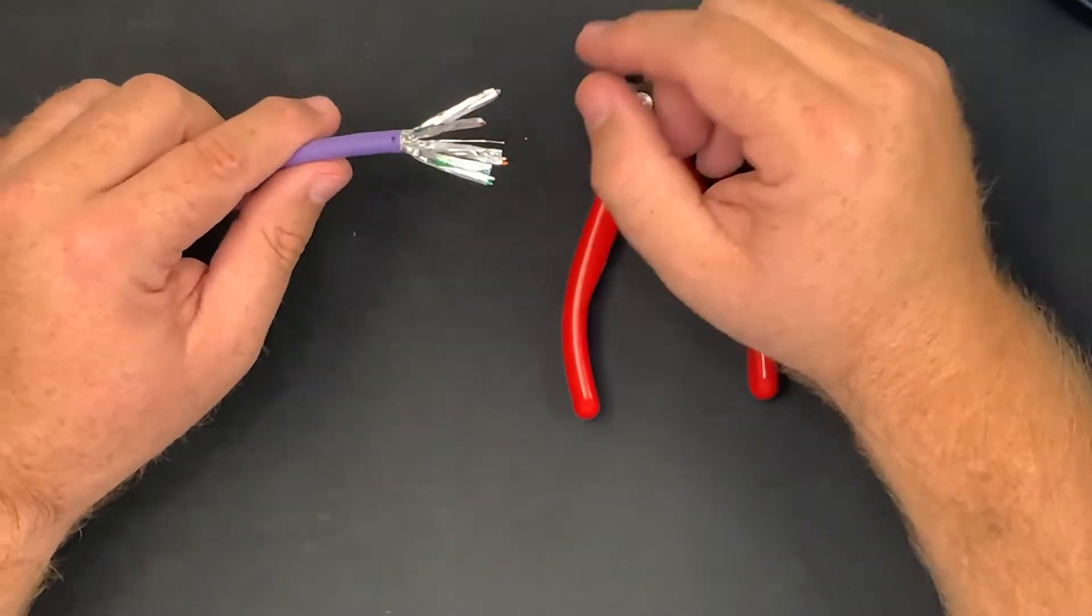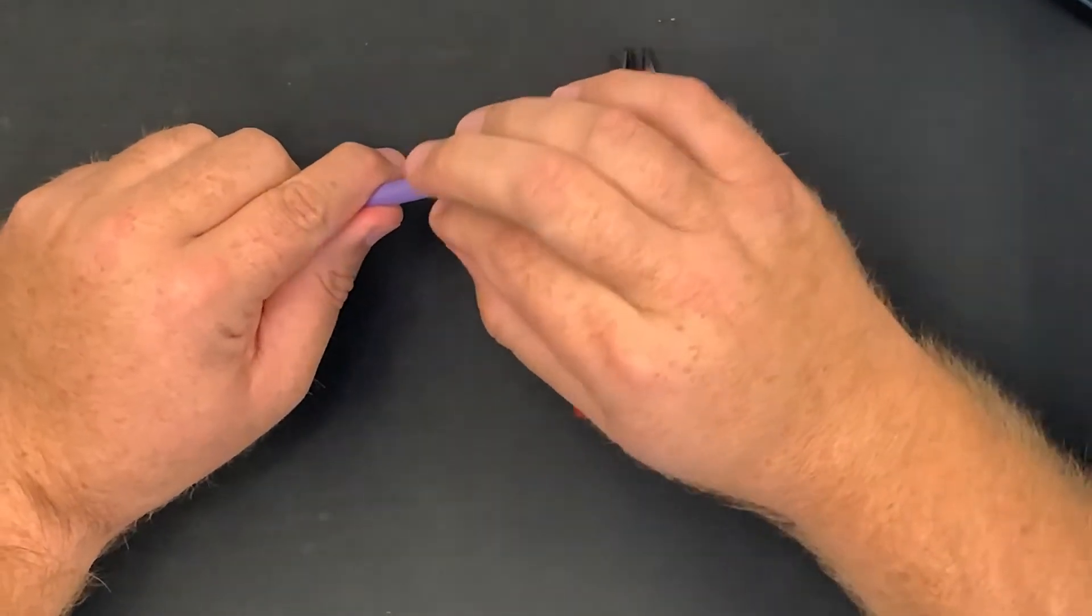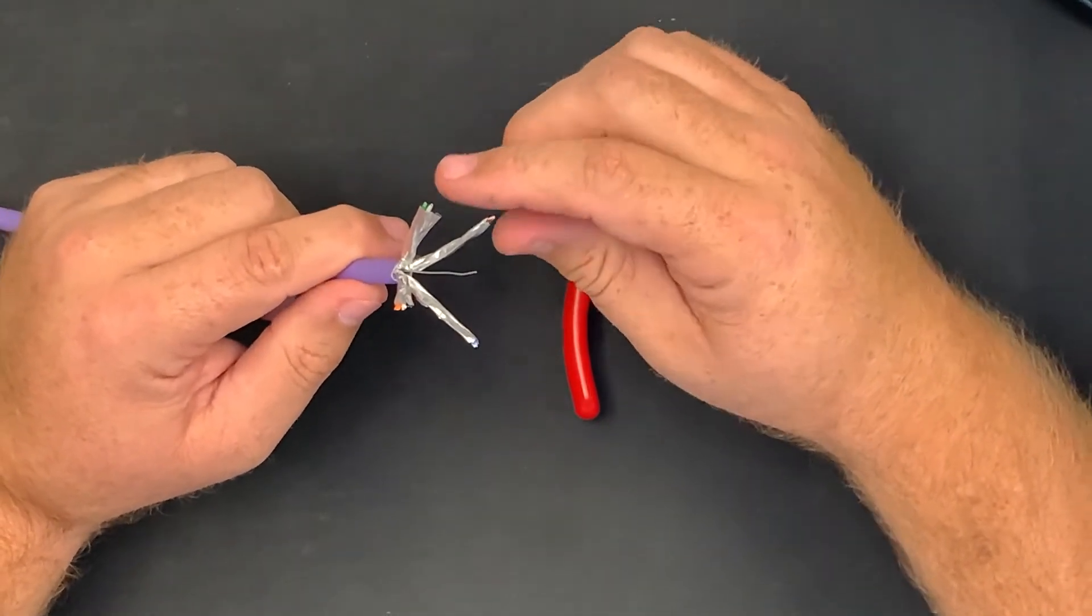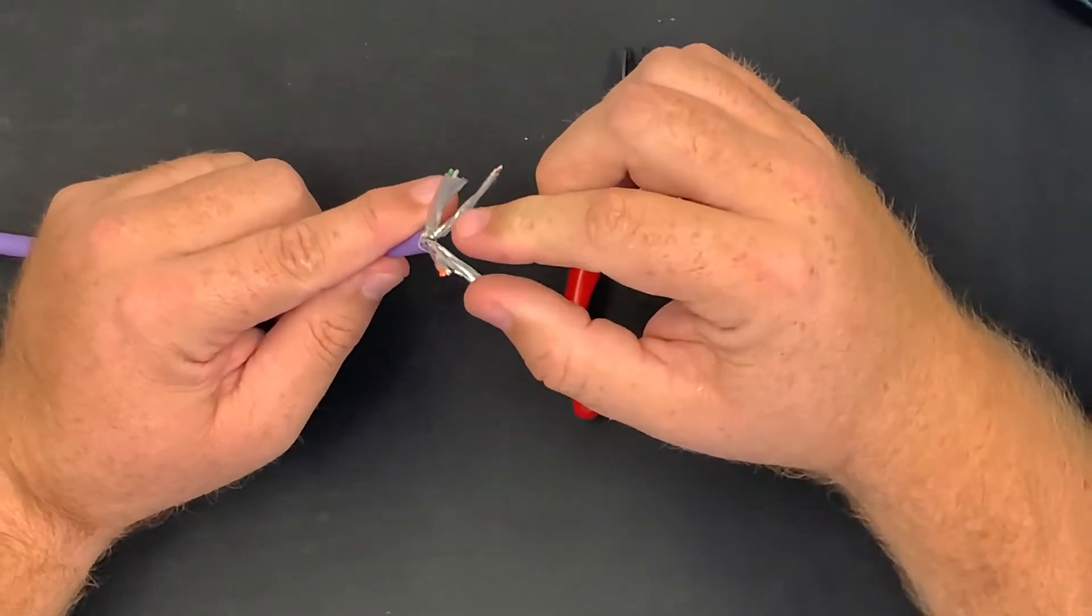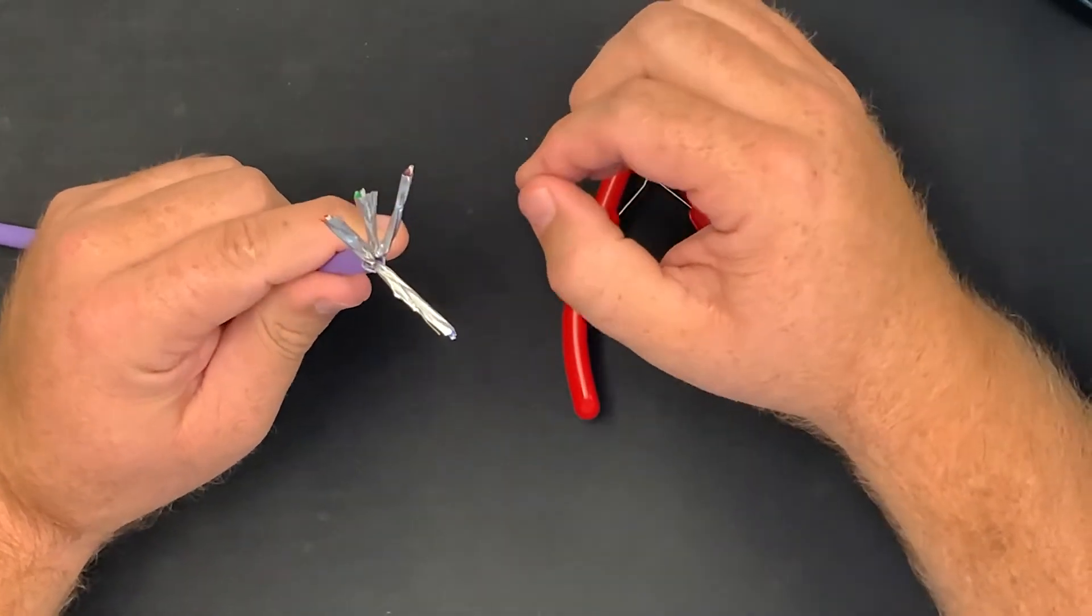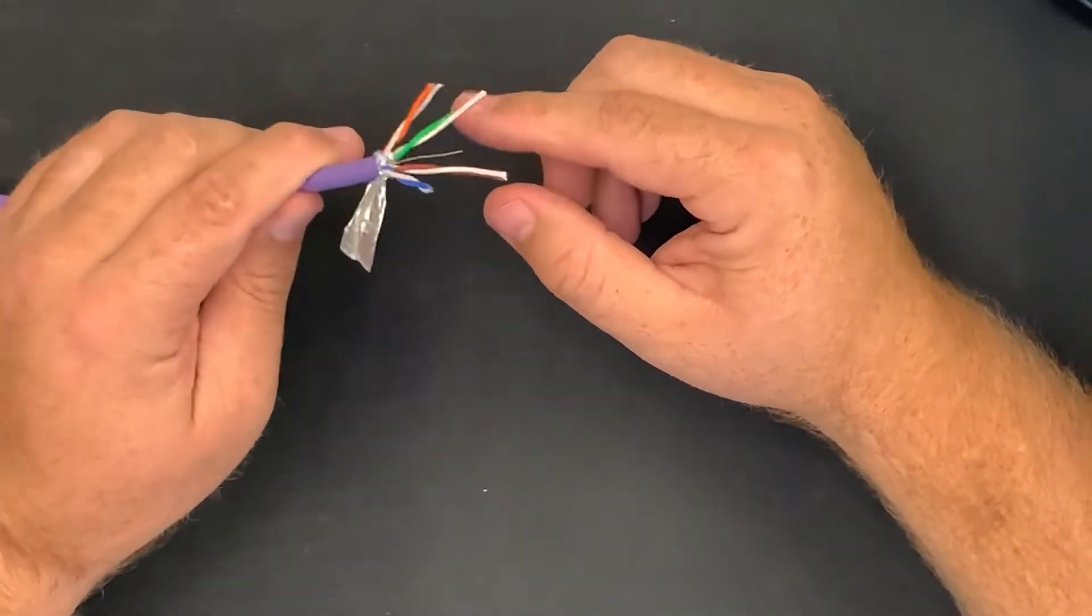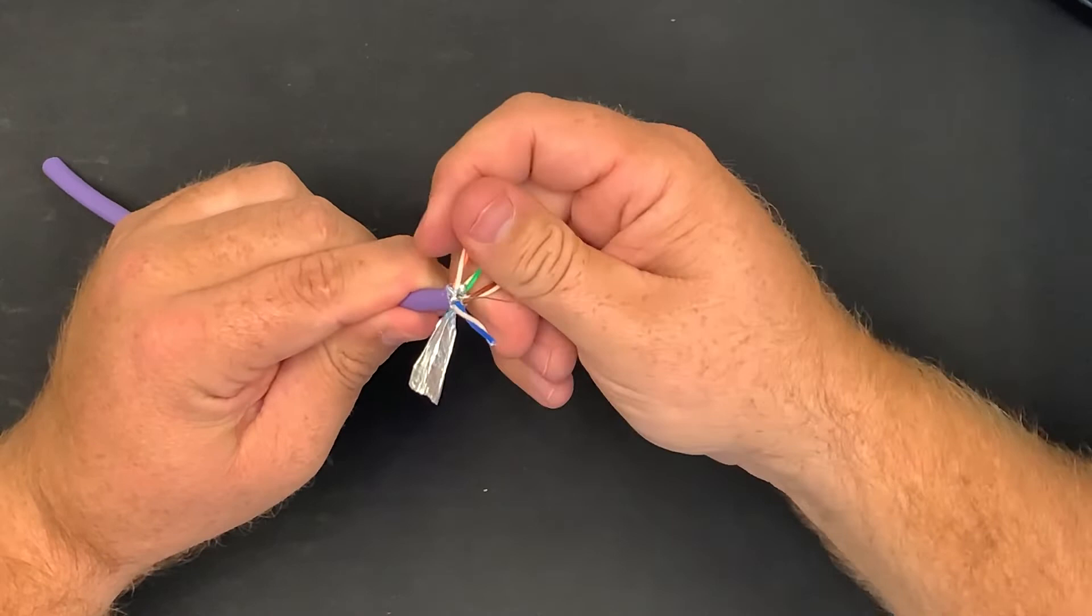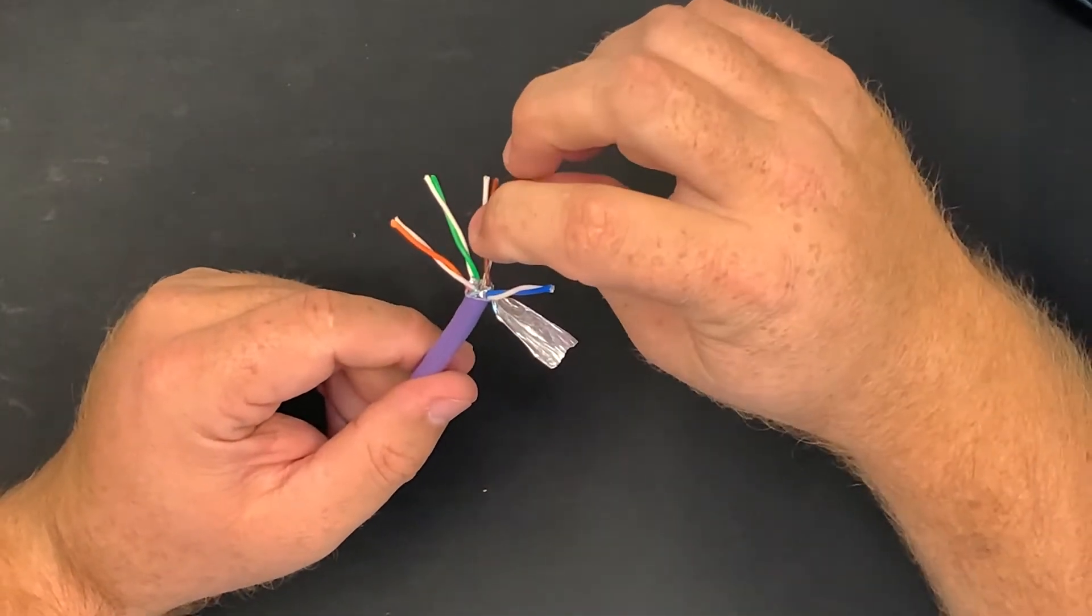After you have removed the cable jacket, you will see that all the pairs have foil around it and you have a drain wire. Now, what you need to do now, you can leave one foil on a pair with the drain wire and you can remove the other pairs. You can remove it from the pairs and cut it off. Now, you will see I have removed three of the foils on the pairs. I have one foil I have left and the drain wire.